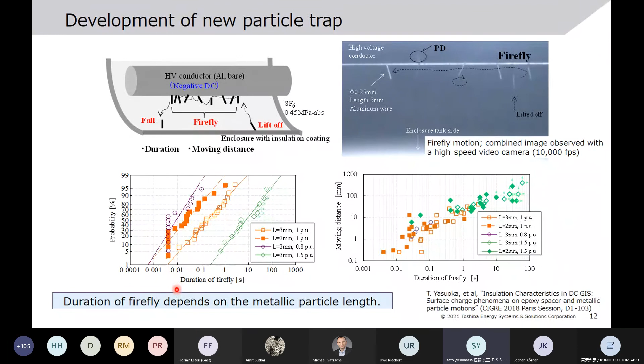And next is the investigation of effects of particle trap. We also prepared a busbar model of this GIS, as the photo shows, and also we used a high-speed video camera, and we took movies through the glass observation window at the end of the busbar. And inside of the enclosure, we put some metallic particles here, and we applied negative and positive DC to the high voltage conductor. And we observed that at the high voltage side trap, the firefly particle easily falls into the grounded enclosure side trap, and under normal operating voltage, it will never lift up again because of the low electric field there.